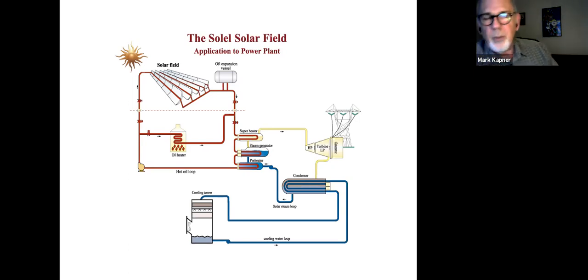Rather than use water, which would have to be pressurized since it boils at 212 degrees Fahrenheit at atmospheric pressure, they use a synthetic oil called a heat transfer fluid. That oil is piped through the tubes receiving heat from the parabolic mirrors, and goes to a heat exchanger that takes the heat from the hot oil, boils water, and superheats the steam, which then goes to a conventional steam turbine.